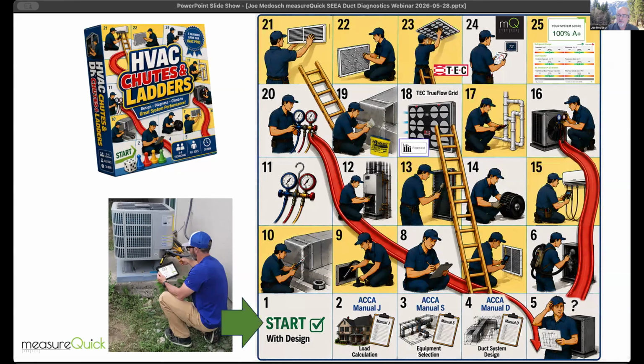But in general, notice the slides that are taking you back down. If you're just going to the refrigerant side, if you're only using your gauges, you are falling back to the question mark, scratching my head, on number 5 because they didn't do their assessment. They didn't use the TrueFlow grid. They're bypassing the tools that are out there for them. So unfortunately, number 5 is a common scenario where people can't figure out why adding or removing refrigerant is not the answer.